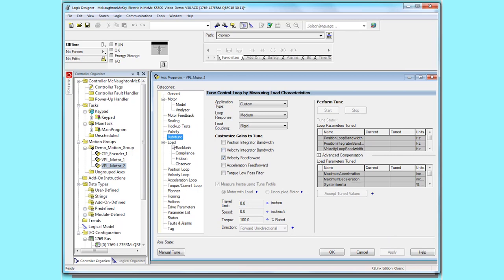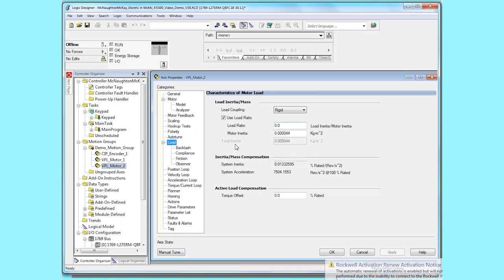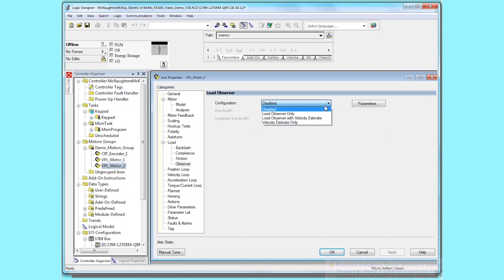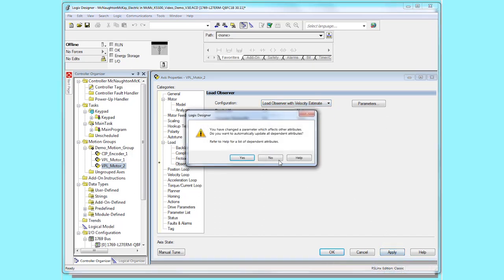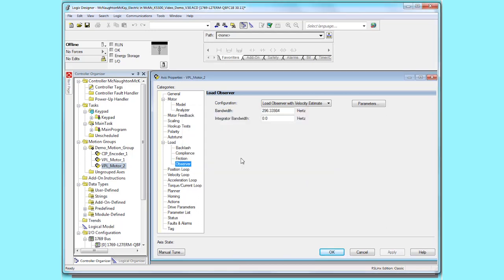We'll go to the load category next and verify that the load ratio is set to zero. Next we'll go to the observer category. The configuration defaults to disabled. We'll pull the pull down down and select load observer with velocity estimate. Click apply and yes to accept those changes.